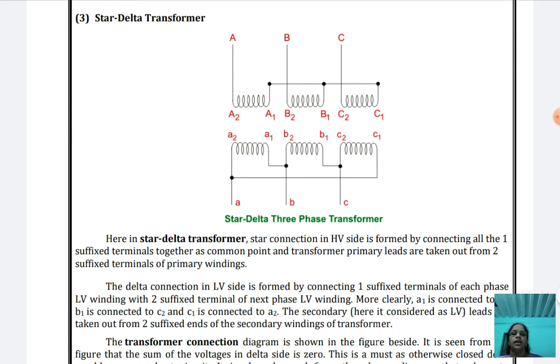Then the star delta connection. In the star delta connection, you see, the capital letter means the HV winding. The HV winding is a star connection and the LV winding is the delta. Here there is no primary and secondary. Listen carefully here: the labeling by capital letter and small letter only represents the high voltage side and low voltage side, not the primary and secondary of the transformer. So this is very important. The star delta connection of a three-phase transformer is nothing but capital letter HV side star connection, LV side delta connection only.